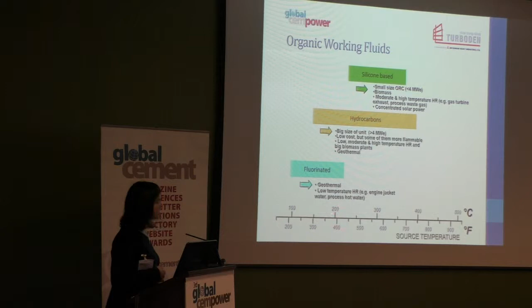Low temperature applications, like geothermal applications, mostly use fluorinated fluids or some hydrocarbons. When we go to medium to high temperature applications, higher than 200 to 250 degrees, the two most used families of fluids are hydrocarbons or silicone-based fluids.